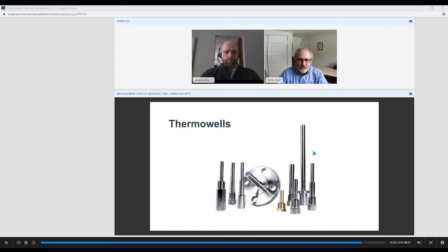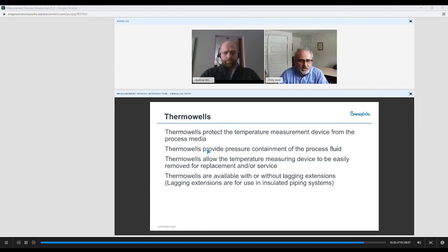I'll talk briefly about thermowells. So a thermowell would meet ASME code. It could be a flange, they can be tapered, they can be threaded. But you would put the thermowell into your system, very robust, machined from stainless steel. They would go into the system, and then the stem would sit inside this. Some of the advantages being that you don't have to shut down the system to remove a thermometer if you have an issue with it and it has to be taken out.